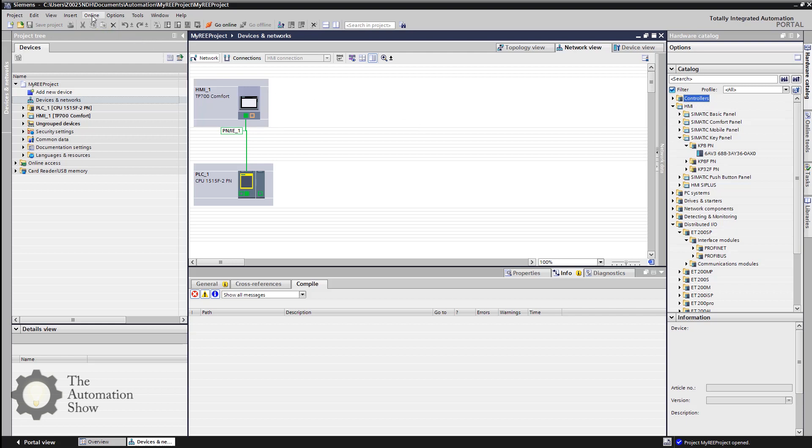Now we want to integrate the drive and motion functionality into a technology object within the PLC so that we have speed control and motion control in our PLC. This makes it easier to implement complex things like positioning and kinematics, or even simpler things like a speed axis. There's a nice wizard that allows us to make the connection from a default motion object to an actual hardware drive — we just map out the graphical connection. We'll accept the default parameters and load that motion configuration into the online PLC.